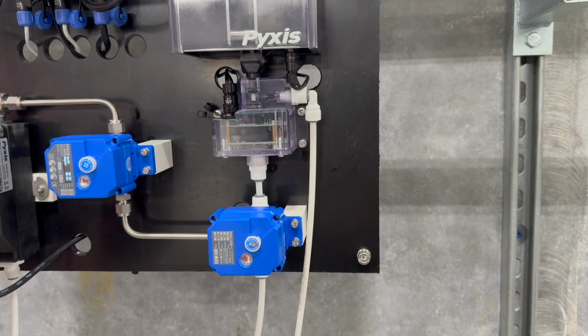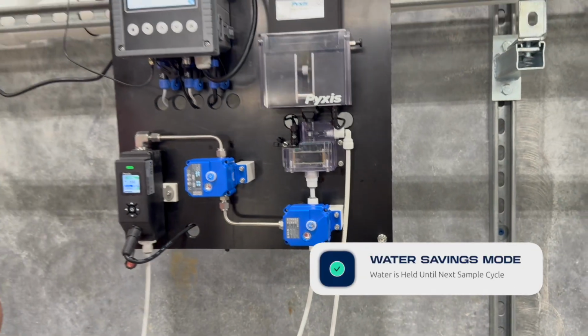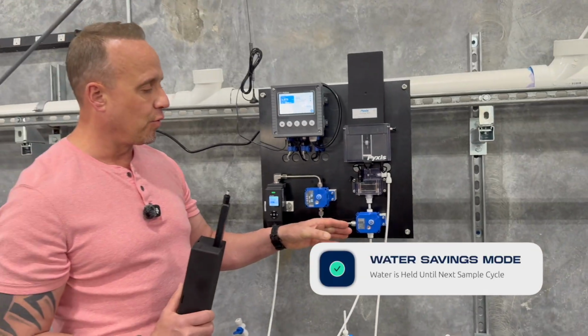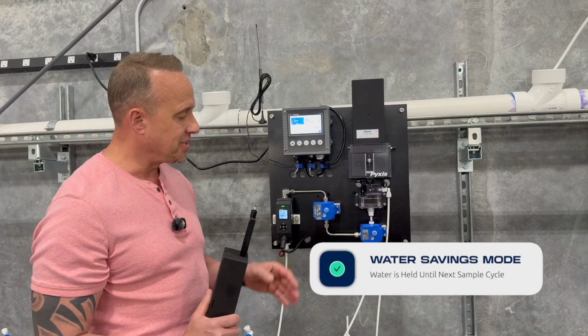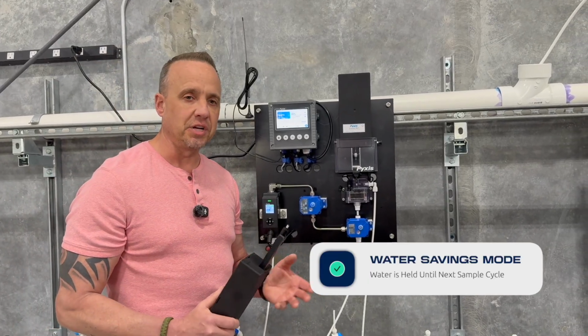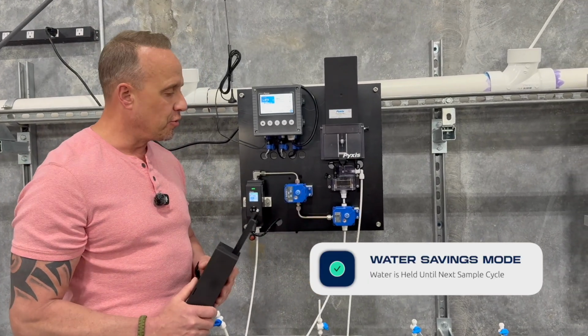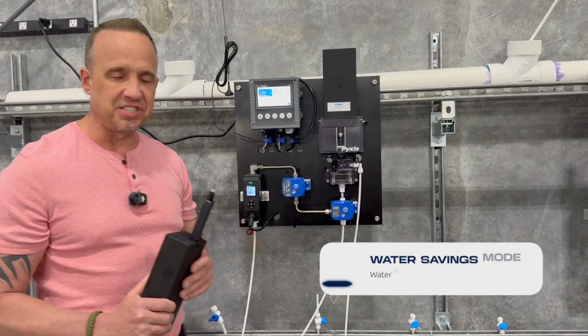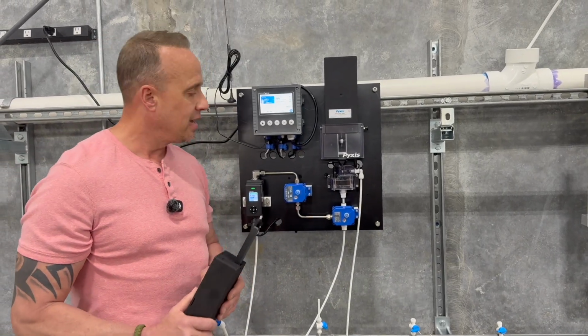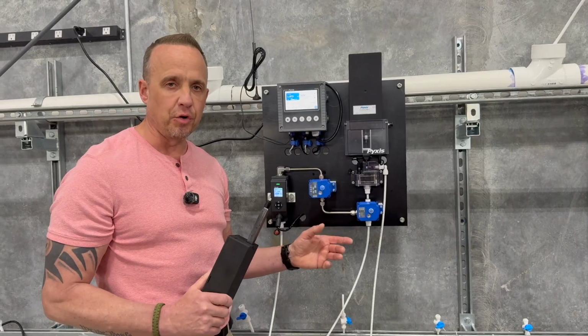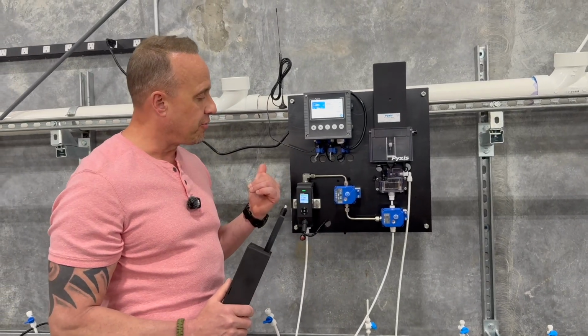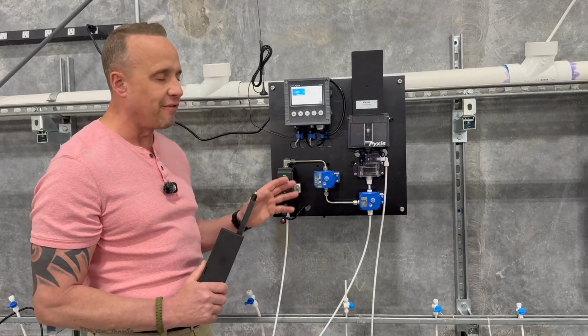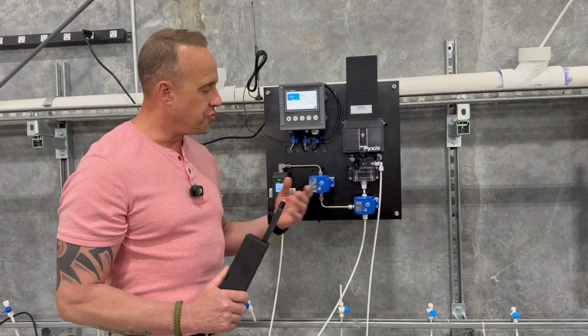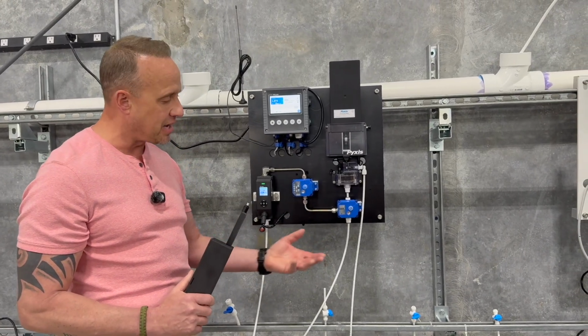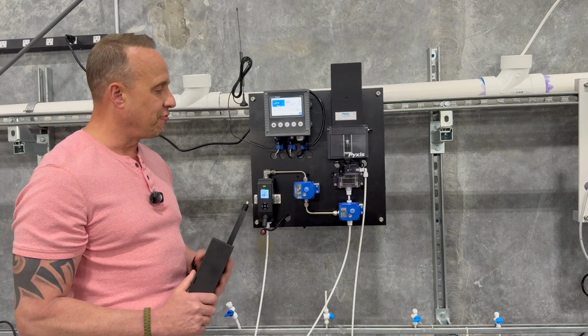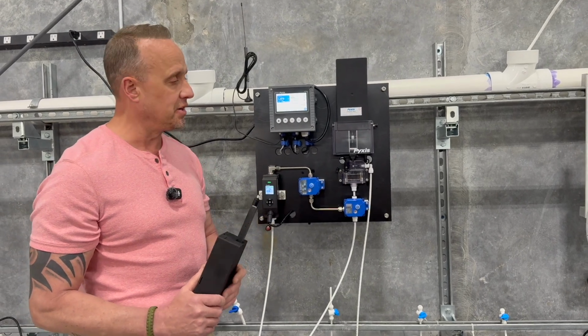But we also offer what's called water savings mode, and in water savings mode, this 3-way valve will remain in a closed position and essentially wait the duration of time until the next sample cycle. Those are for applications where the customer is very sensitive to water consumptive use and they want to minimize the amount of water going to drain. The HMI offers some customization as to the valve actuation sequence, the duration of the pre-flush and the sample time, as well as the frequency of the sample being conducted itself.